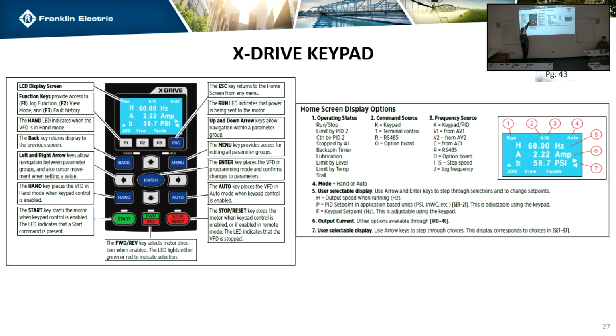The F keys are predetermined by the things that are above them. So F1 is jog, F2 goes through a bunch of view screens. If you keep hitting it, it'll go through a bunch. If you guys want to right now, you can. Later on, we'll go through it to show you what it goes through. And then F3 gets into your fault logs. Menu just rifles through all the different menu options. Back takes you back one screen. Obviously, arrows are arrows, enter key is an enter key.